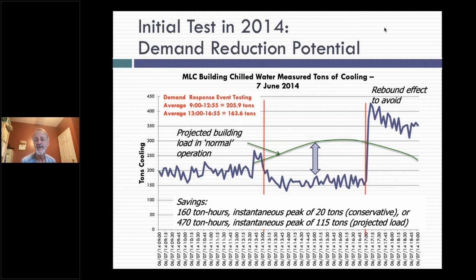In this particular test, we implemented the change at 1 o'clock in the afternoon and went back to normal at 5 o'clock. You can see a big bounce back, the rebound effect. How do we avoid that? Looking at the peak, if we were trying to reduce peak demand on electricity consumption, we didn't affect that at all. In fact it was worse, because the system was trying to recover from the time period when we had a higher temperature set point for cooling.